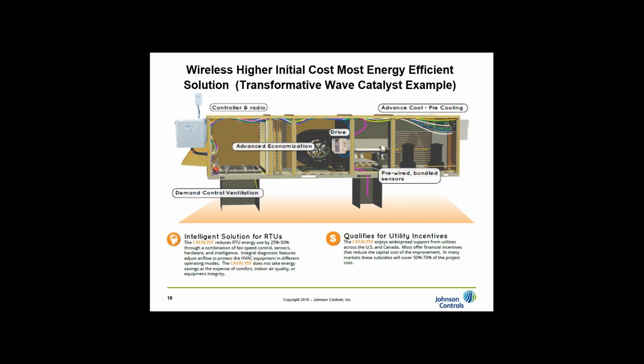What it does is take a traditional constant volume unit, what we call a DX package unit, which is probably what's used to heat and cool 75% of the buildings in the United States, and add a few features to it. It adds a variable speed drive to the fan, and adds what's called demand control ventilation, kind of like indoor air quality control. They basically install an indoor air sensor to monitor CO2 levels and optimize the economizer with that.